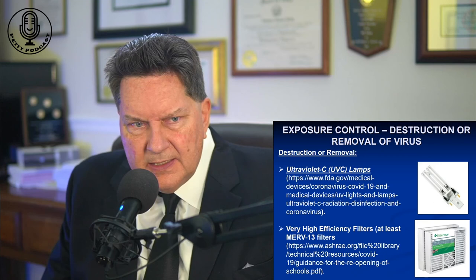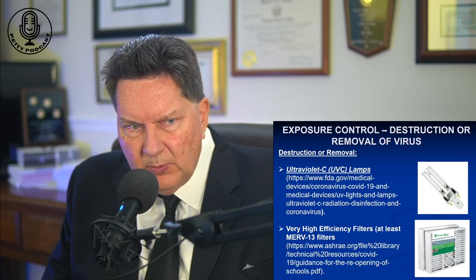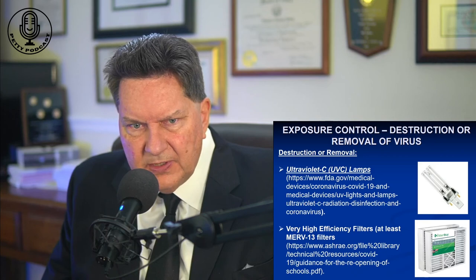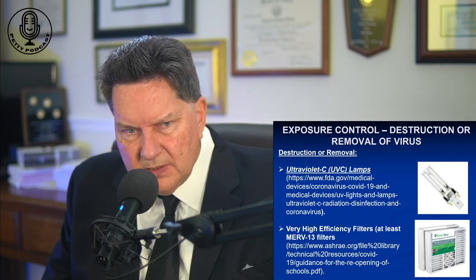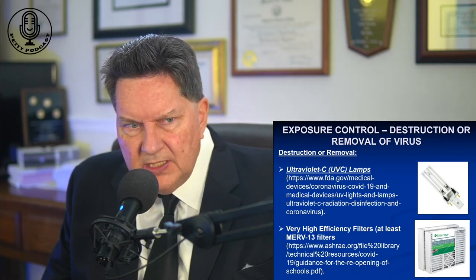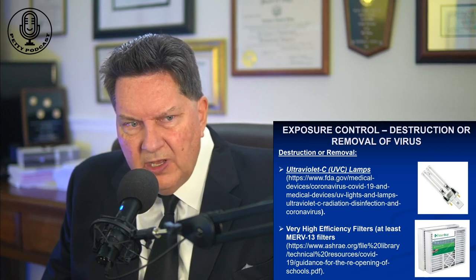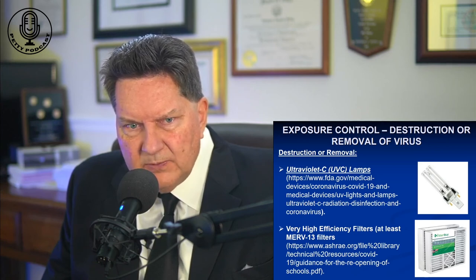Last are high-efficiency filters. These are more for removal of the virus rather than destruction. If you get what they call a MERV-13 or higher — the higher the MERV number, the more small particles they'll remove — MERV-13 is recognized as removing COVID particles. It does come with a higher pressure drop because the filters are tighter, so you use a little more power on your fans and furnaces, and you'll have to change them out from time to time.